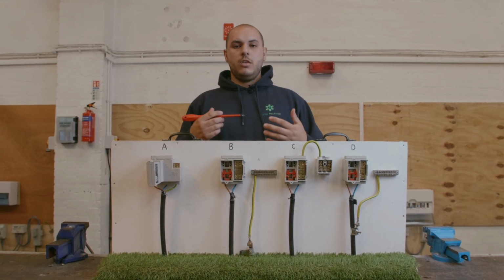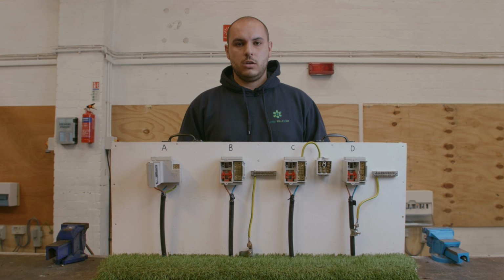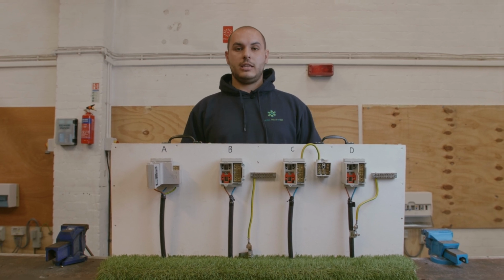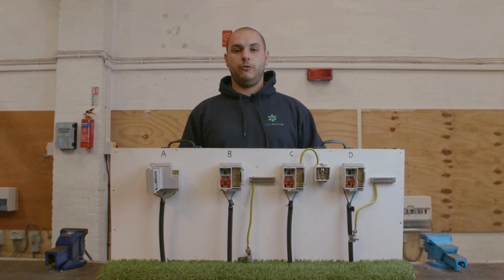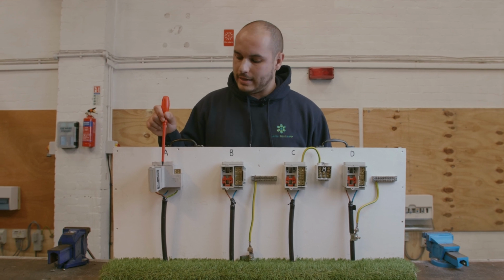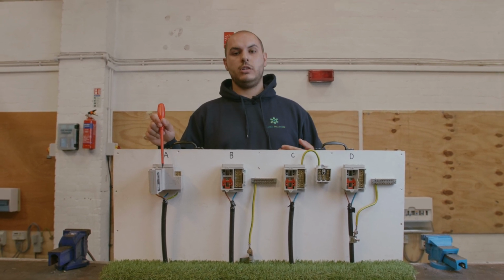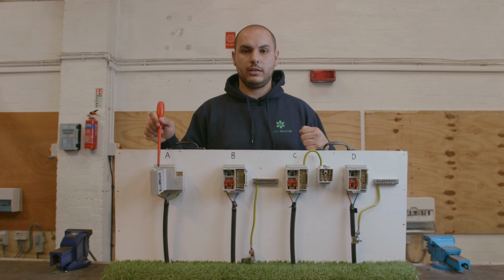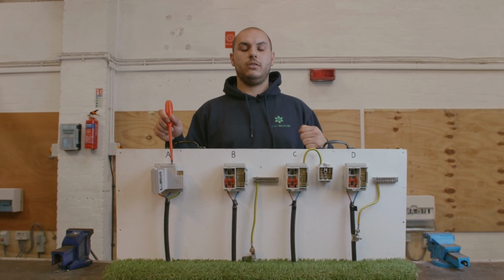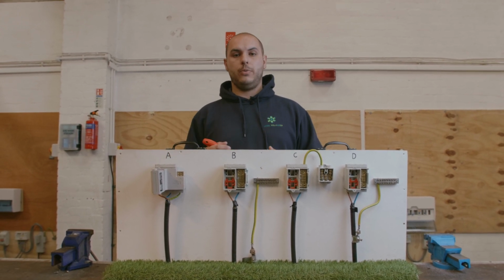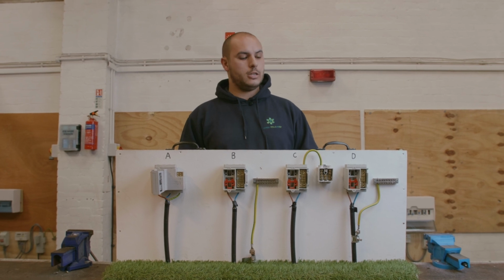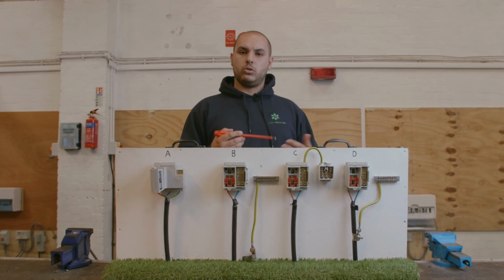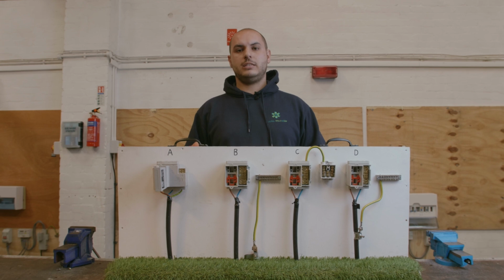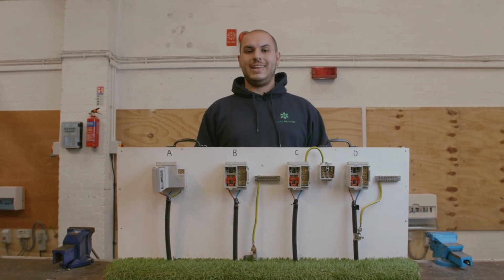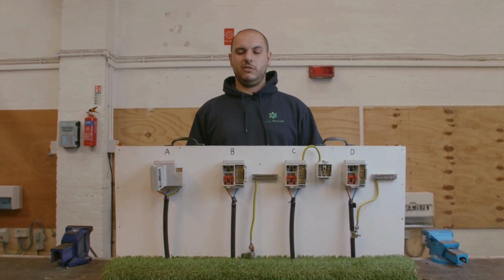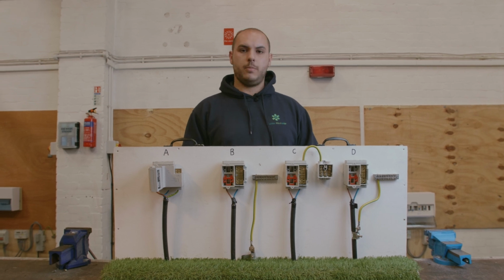Okay. The other variant of these earthing arrangements is the TNS again, but in a different form. So the first one we've looked at is where the supply cable is 3 cores, and it incorporates the line conductor, the neutral conductor, and also the earth, all separate all the way back as discussed previously. But if we go to the next cutout, we can see that the TNS system has been brought in a slightly different setup and a different way. Okay, so let's have a look at that one in a bit more detail.